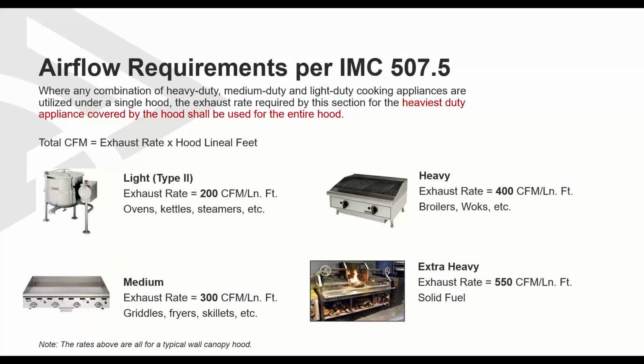Going into airflow requirements, there are requirements per IMC 507.5, where any combination of heavy duty, medium duty, and light-duty cooking appliances are utilized under a single hood, the exhaust rate required by the section for the heaviest duty appliance covered by the hood shall be used for the entire hood. What that means is if you have a broiler heavy-duty appliance and a medium-duty griddle, the exhaust rate must follow the heavy-duty rate for the entire hood.